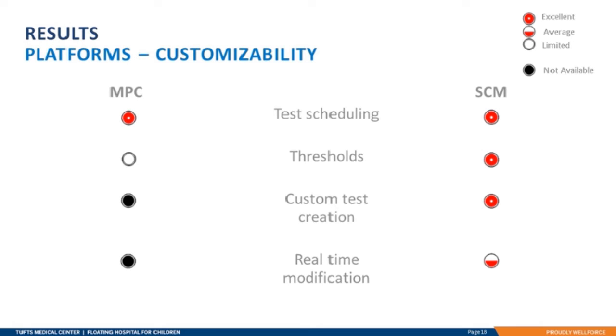Next is customizability. Both platforms really are nice in the ability to schedule tests. For both, individual tests can be scheduled according to the day of the week. The only nuance that we didn't originally appreciate is that the radiation therapist account settings in SunCHECK Machine doesn't show tests as available if they aren't scheduled. Therefore, we modified our scheduling so that the full QA was available on Saturdays and Sundays in case of emergency treatments.